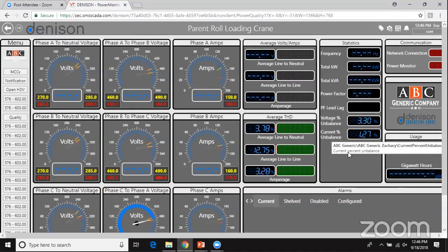Unlike where the screen is showing right now, if it were green and we were connected, the data would be flashing at us and we'd see different trending. As Matt talked about before, the box closest to the right of communication shows your statistics - we're pulling frequency, kilowatt, kVA, power factor, some voltage and current imbalances. And the big green squares in the middle show total harmonic distortion. Dean, if you could click on one of those big green boxes - say I'm the operator playing for the day, I want to see my historical data viewer.